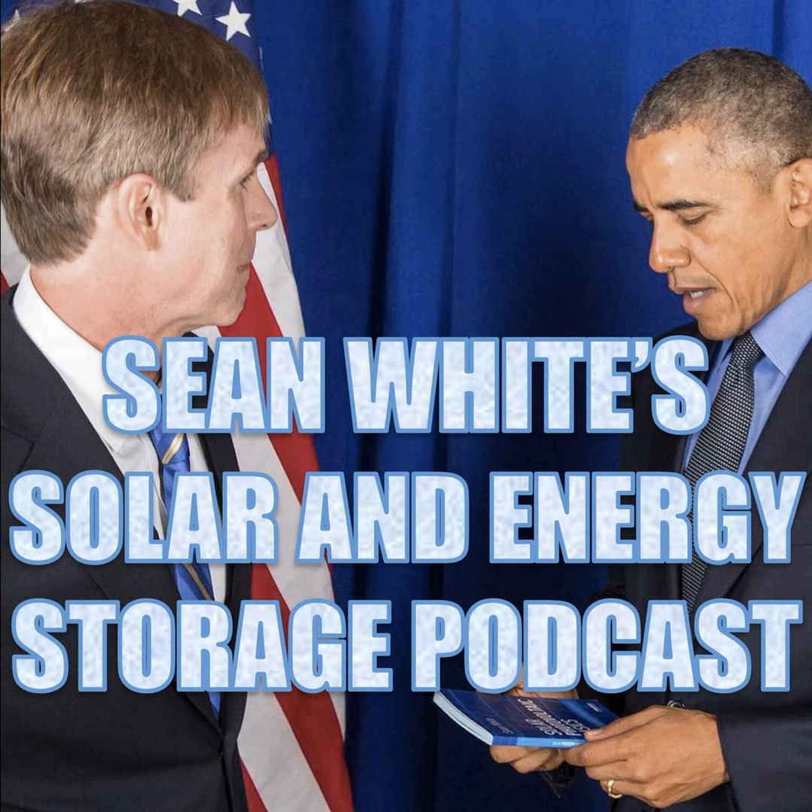When energy storage units are closer than three feet to each other — say the unit has been provided with large-scale fire testing to show that units can be installed as close as one foot apart — the Tesla Powerwall is a good example: they put them right next to each other, essentially touching with a half-inch gap, using a separator. You can do a double stack or a triple stack, and that's been fire tested. Each individual unit is around 13–14 kilowatt hours, so a triple stack would be just over 40 kilowatt hours.